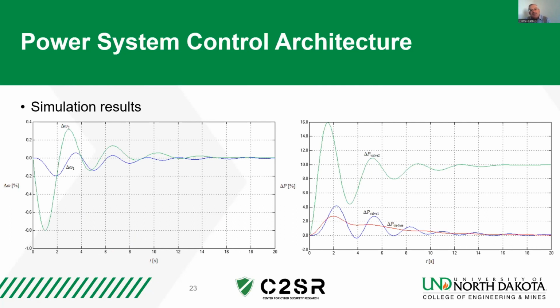Both areas try to respond. Area number 2, actually, we have a change. Area number 1 gets 10 megawatts more power. Area number 2 dampens out, and the frequency dampens out, and the tie line power returns back to its normal level of operation.